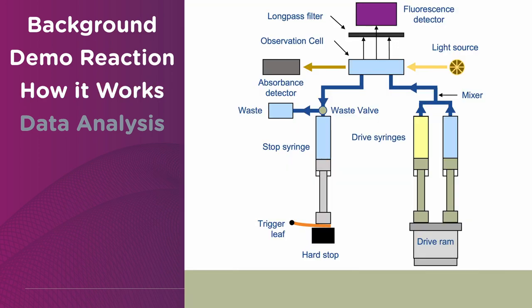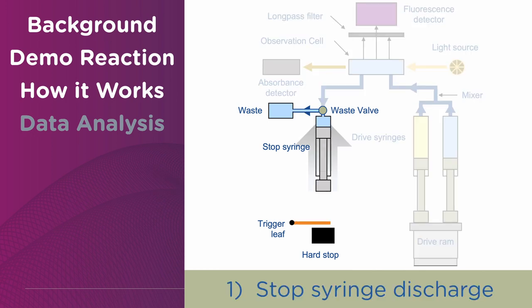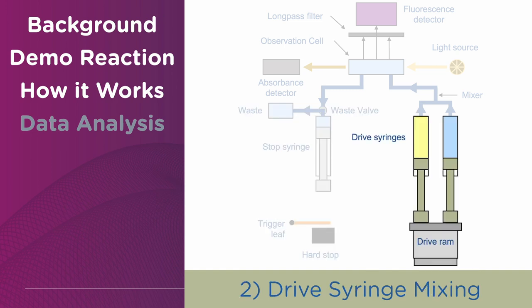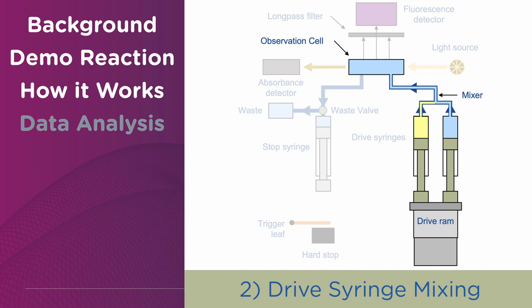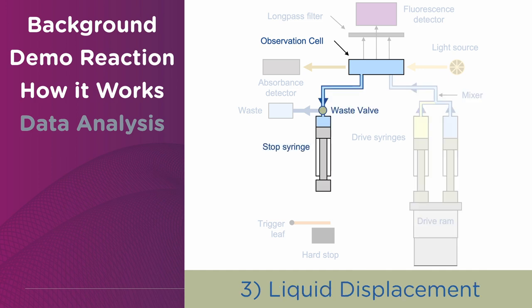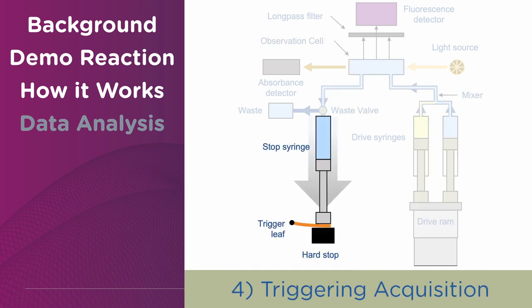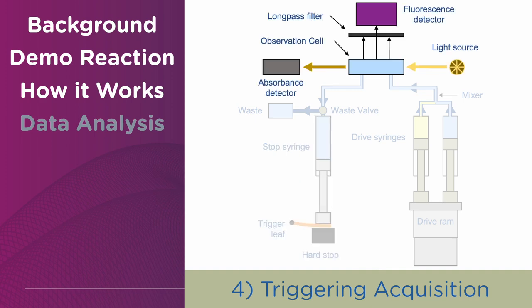A standard stop-flow mixing experiment, like recording absorbance or fluorescence, is automated and the runs are repeated in a sequence where first, the excess liquid is discharged from the stop syringe into the waste, and then defined volumes from drive syringes are mixed into the observation cell. This creates a displacement of liquid, which then travels down the stop syringe, activating signal acquisition with minimal millisecond dead time.